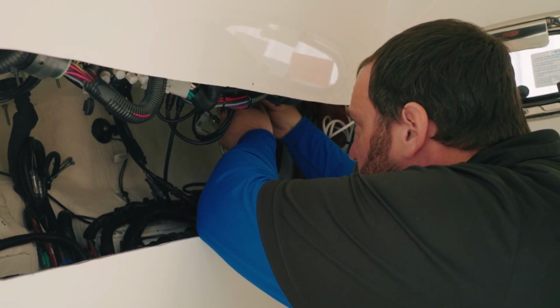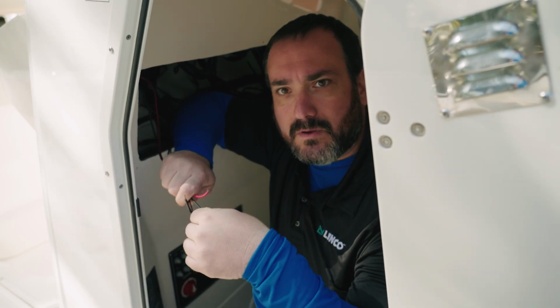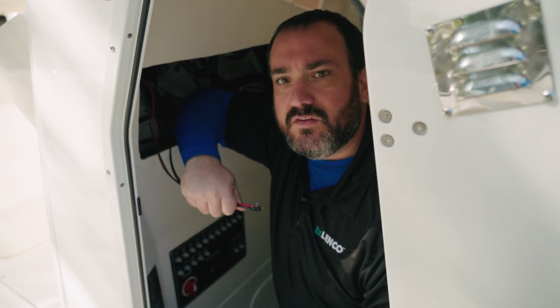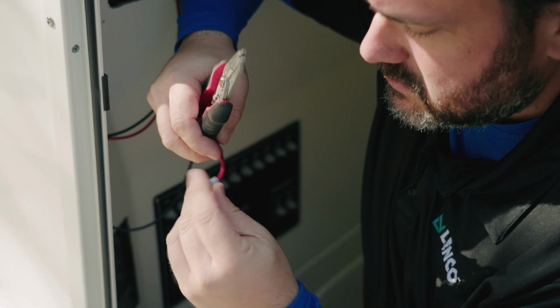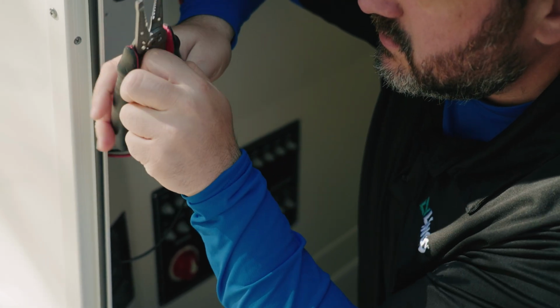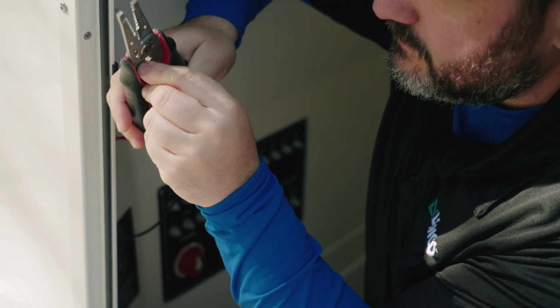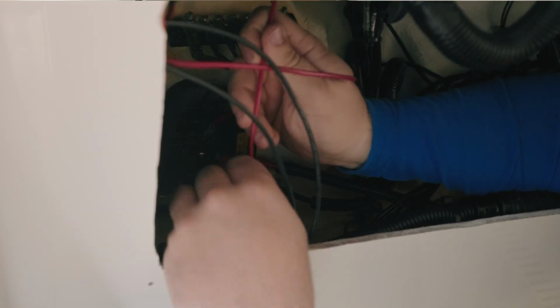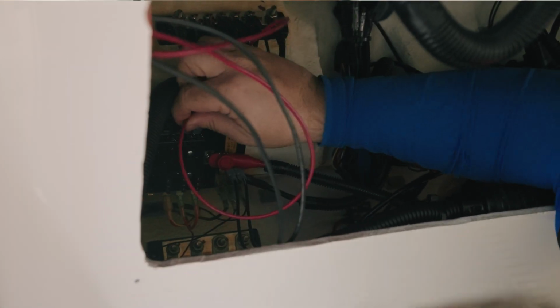All right, so now in the console, we are going to grab our actuator power leads and wire them into power for each individual actuator. They also require 20 amp circuit protection per actuator. In this case, as opposed to using the supplied inline fuse holders, we're actually going to connect into a pre-existing fuse block that's inside the boat.